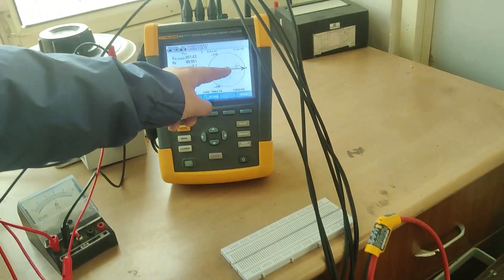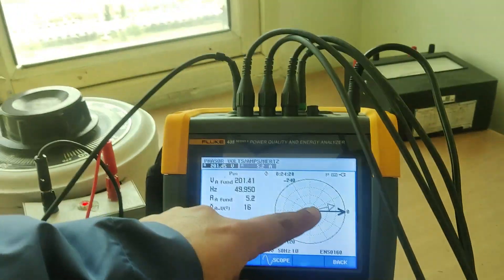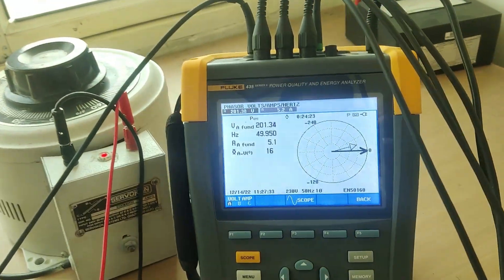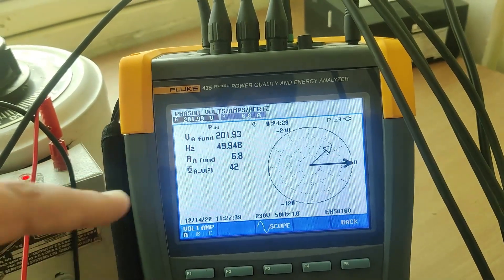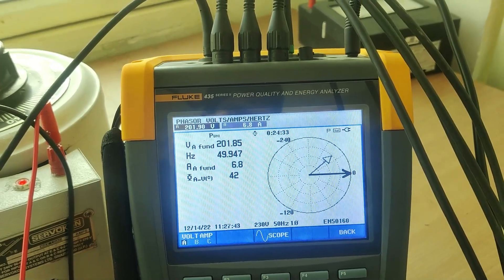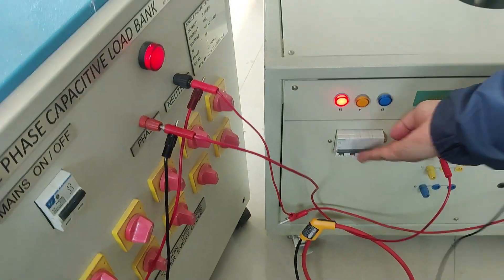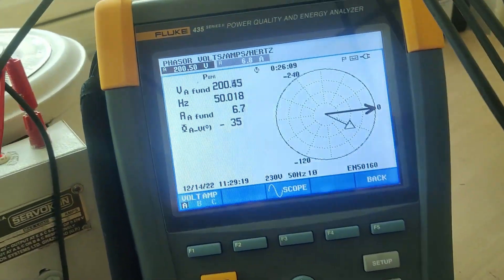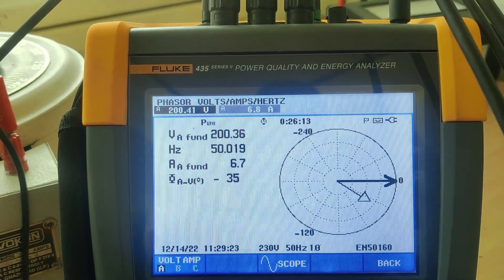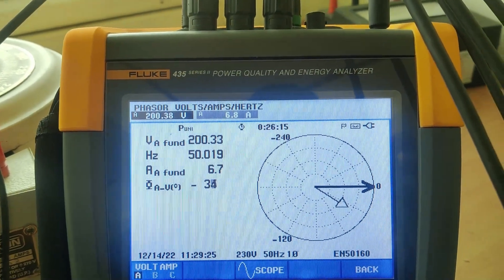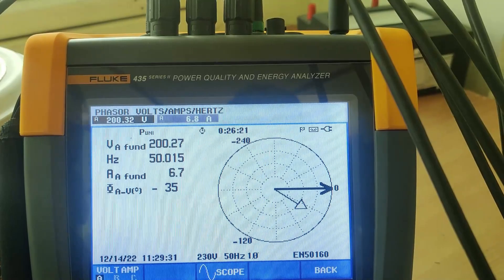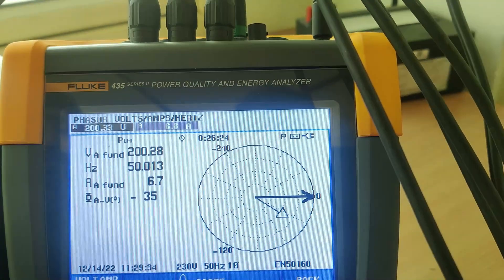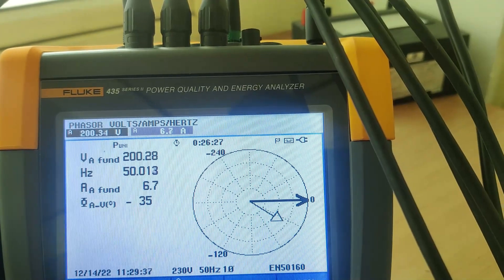When I add capacitance, you can see the angle has increased — the current is now leading the voltage by some angle. As I increase the capacitance further, you can see the phase angle keeps increasing. Now I will switch on the inductive load bank in parallel. When I switch on the inductive load, you can see the current is now lagging, which means the inductance is now dominant.